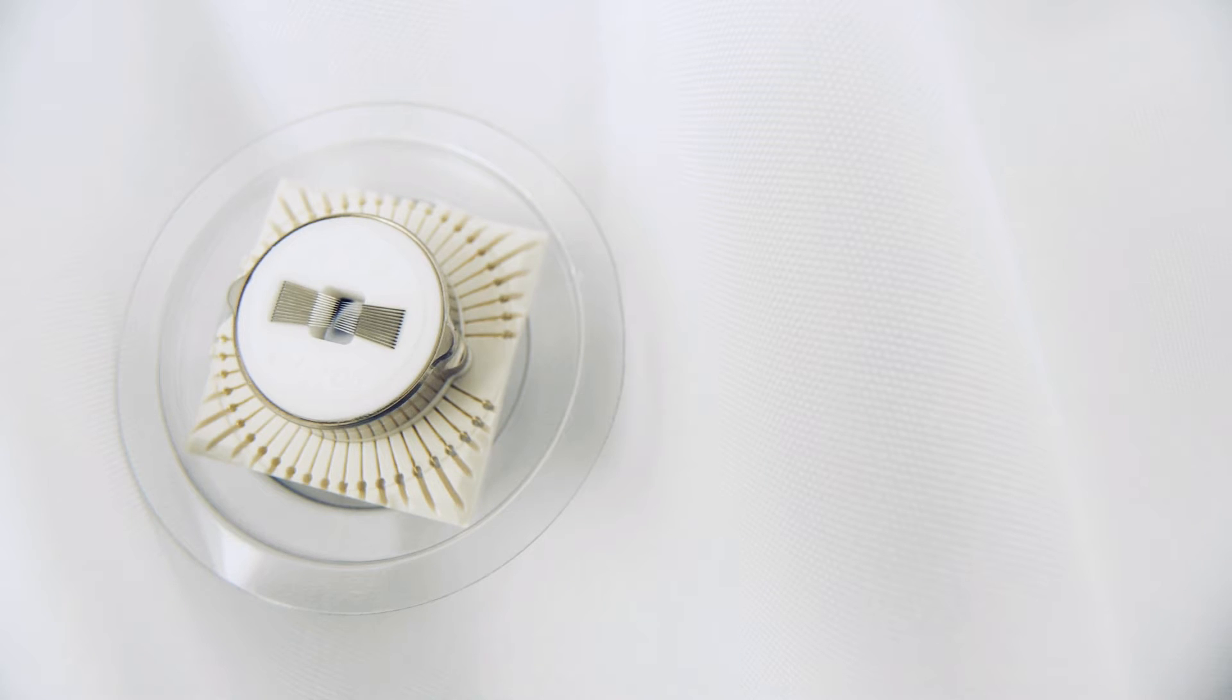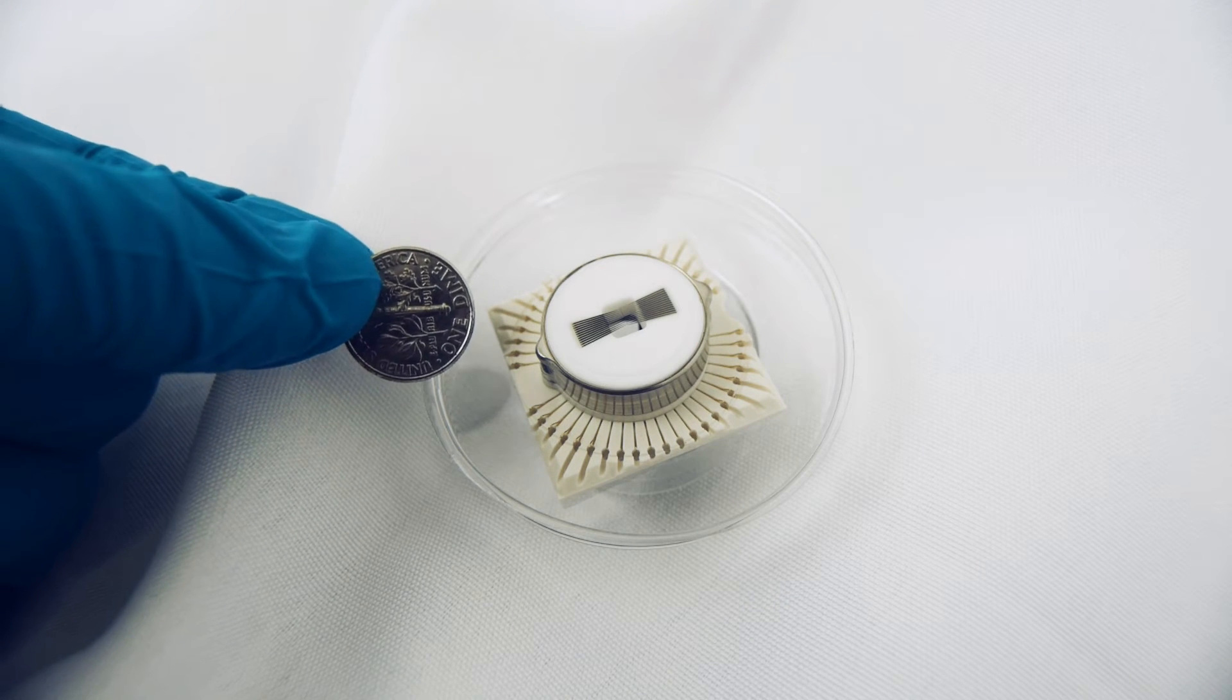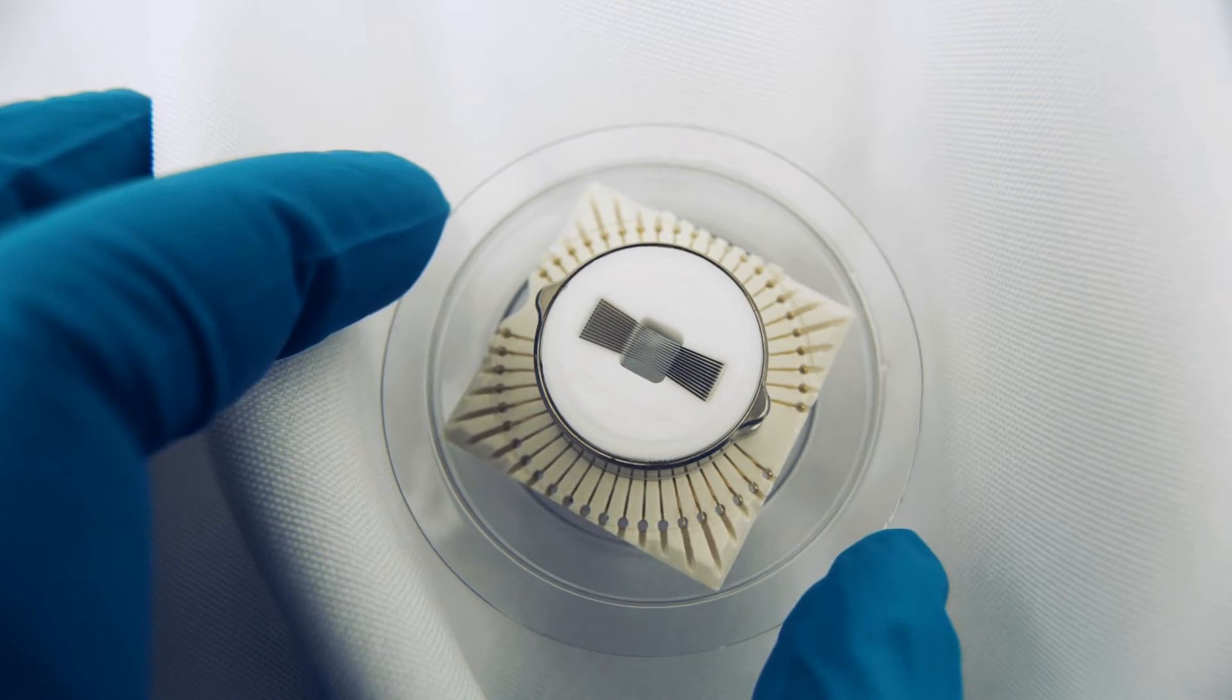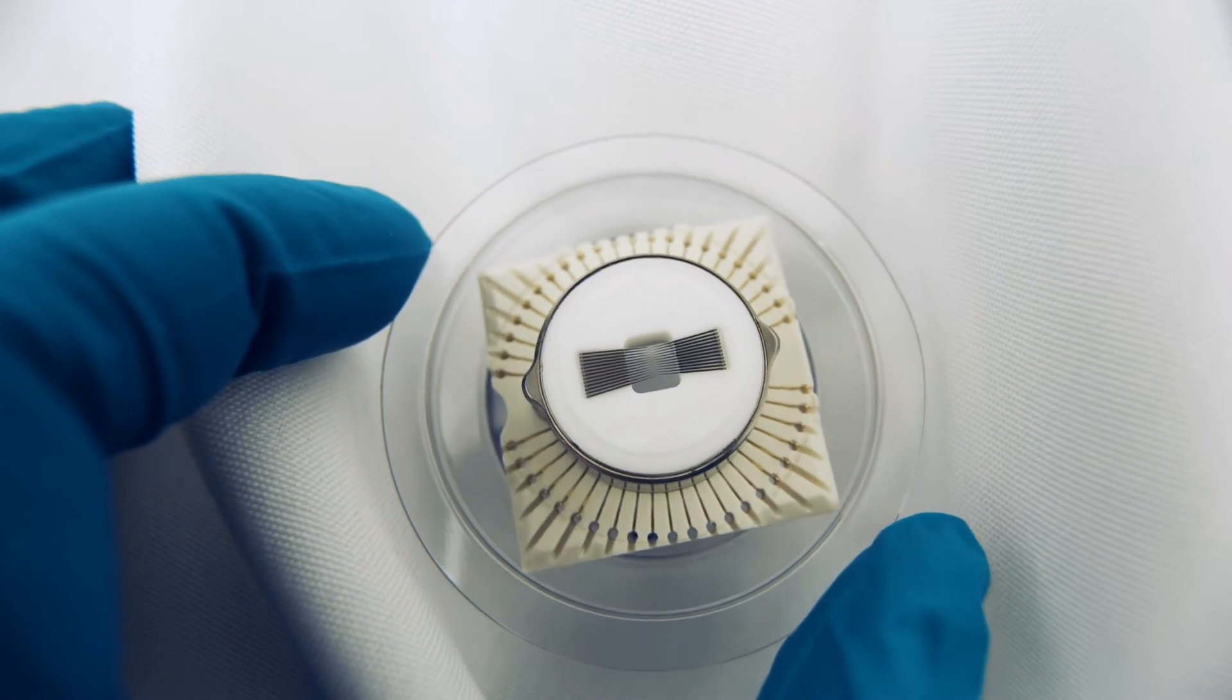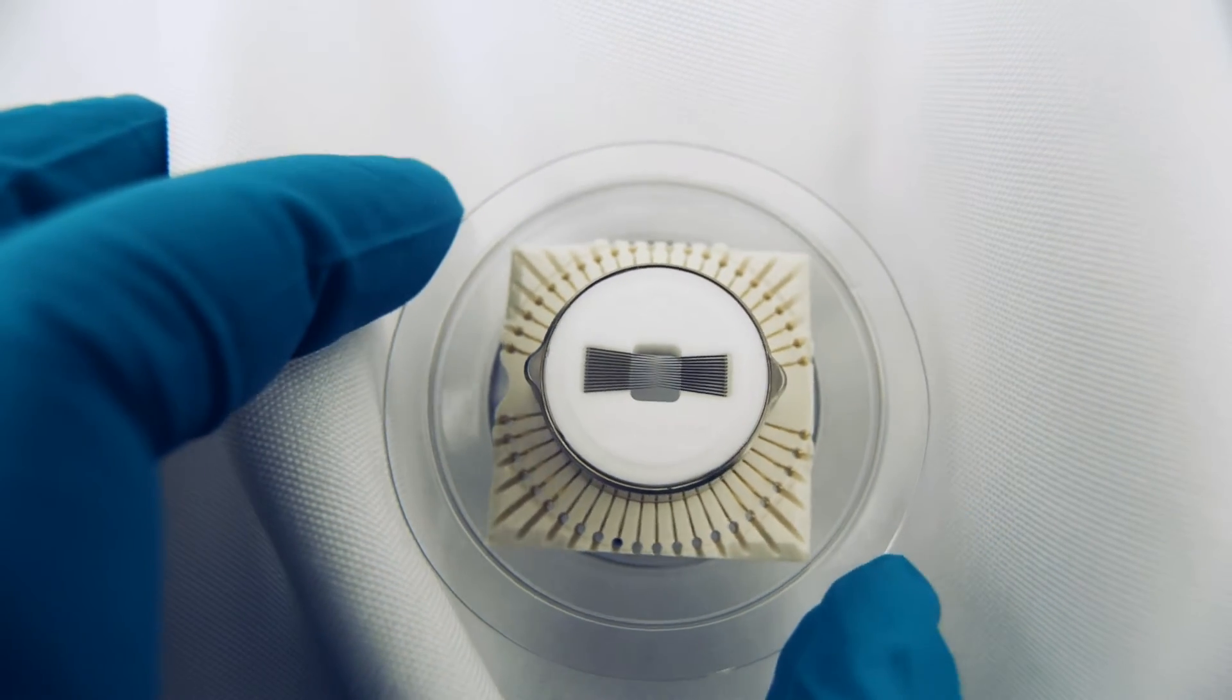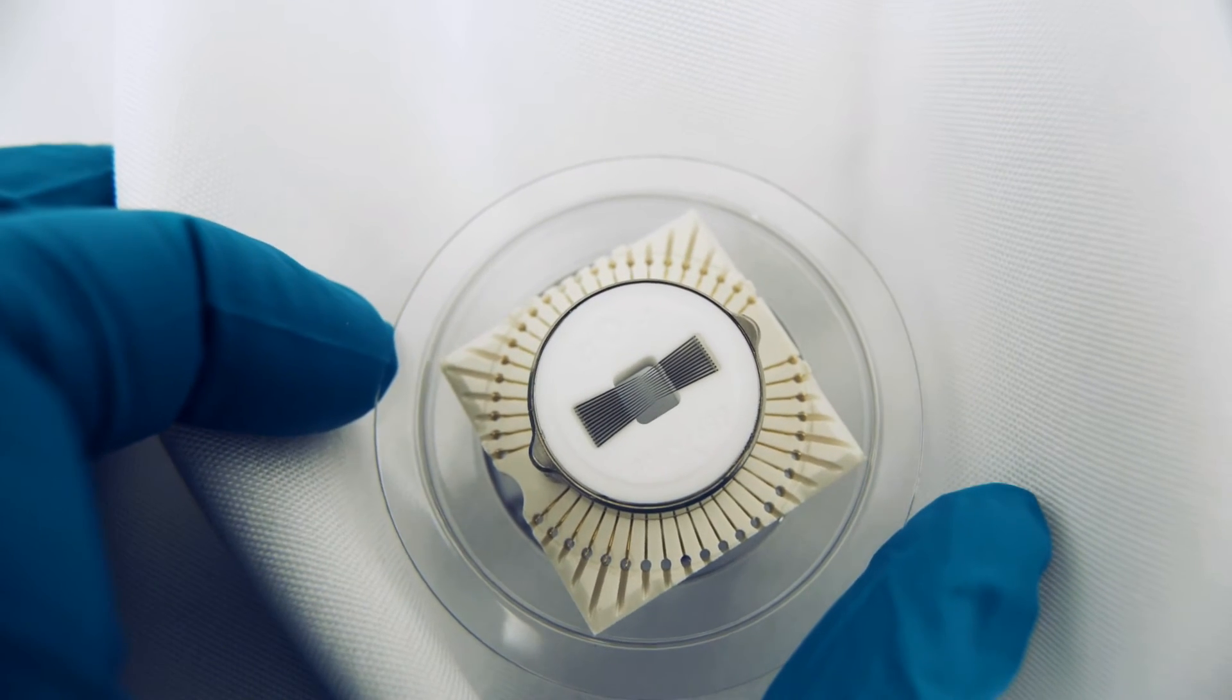The VC20 can be outfitted with up to 48 probes, despite being the diameter of a coin. It can operate in temperatures from negative 65 to 200 degrees Celsius, has leakage as low as 5 femtoamps per volt, and probes can be pitched to nearly vertical to minimize scrub length.